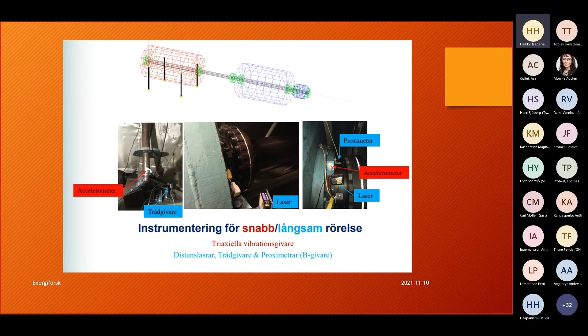Then there are limitations to what you can do on an occasion. Perhaps you have to change the transducer type you've chosen because somebody put up scaffolding in the wrong place. This is actually a pump in one of the stations - I couldn't reach what I wanted to measure, and in this case I actually measured the wrong thing because the scaffolding was improving the stiffness of the system.